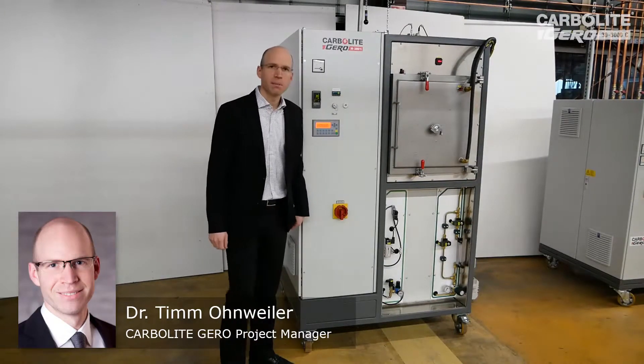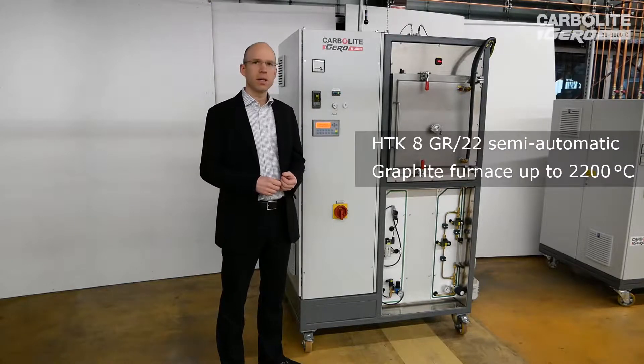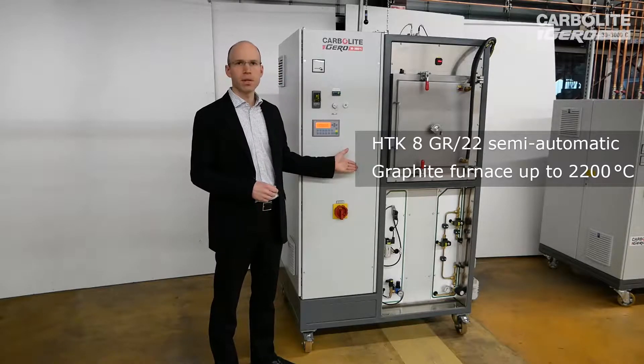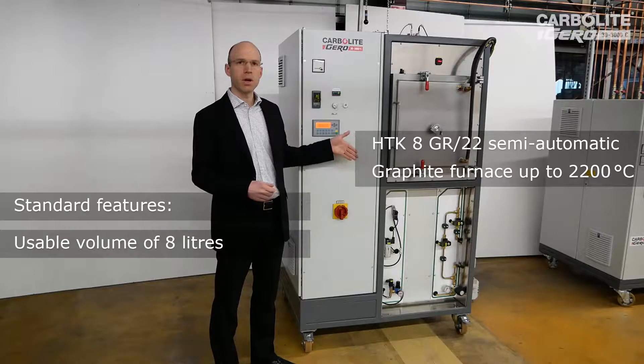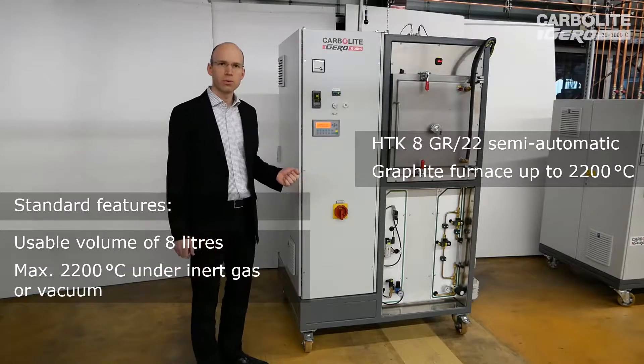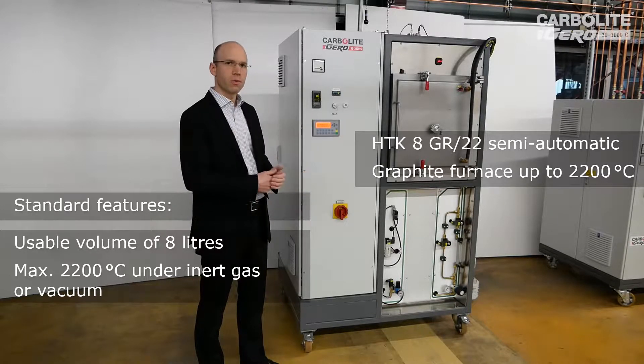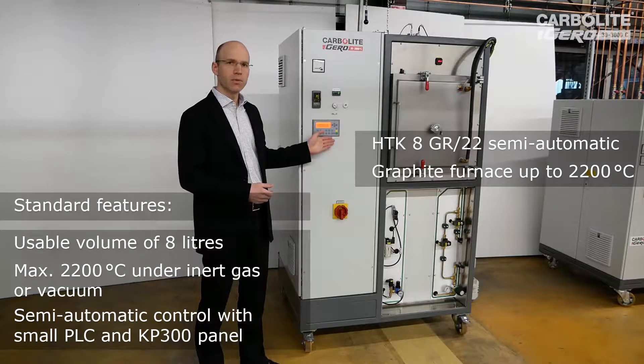My name is Tim Ohnweiler from CarboLight Gero. It's a pleasure for me to introduce today the second standard unit we supply to our customers. This is a chamber furnace of the type HTK. It's an 8-liter furnace, which means we have a hot usable volume of 8 liters. It is a graphite furnace which can go up to 2200 degrees C in this version, but we can also upgrade it up to 3000 degrees C.